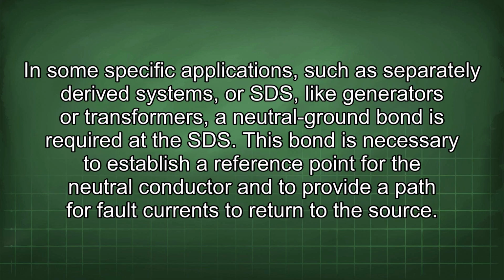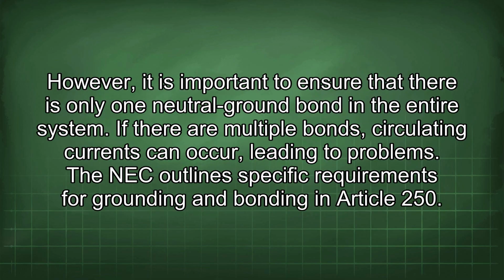In some specific applications, such as separately derived systems or SDS, like generators or transformers, a neutral ground bond is required at the SDS. This bond is necessary to establish a reference point for the neutral conductor and to provide a path for fault currents to return to the source. However, it is important to ensure that there is only one neutral ground bond in the entire system. If there are multiple bonds, circulating currents can occur, leading to problems.